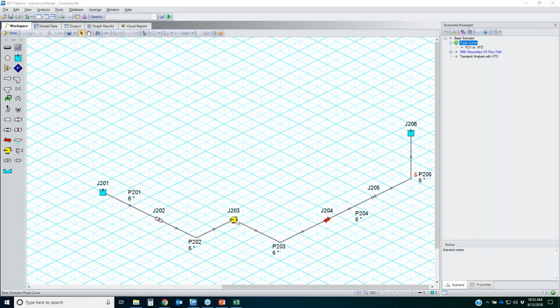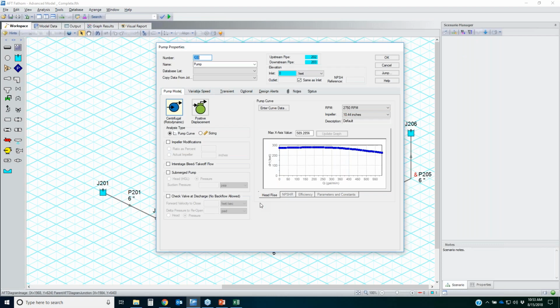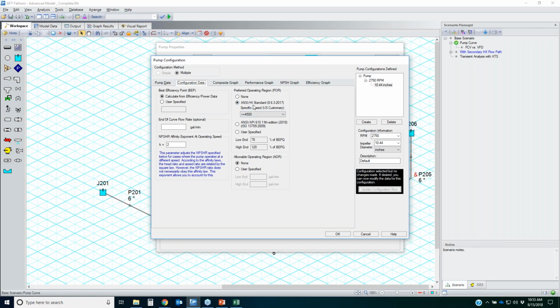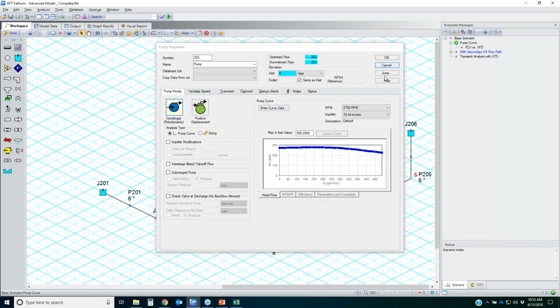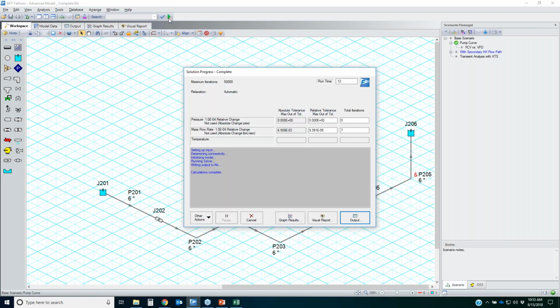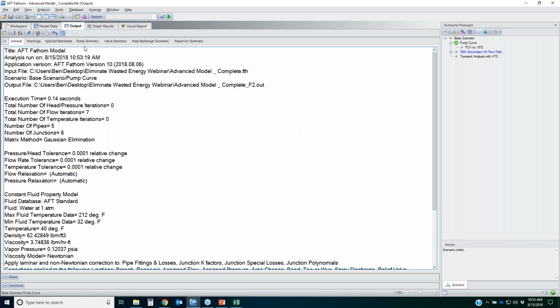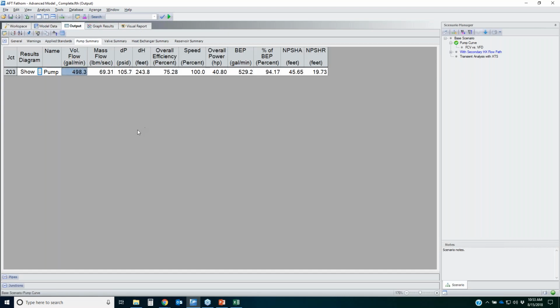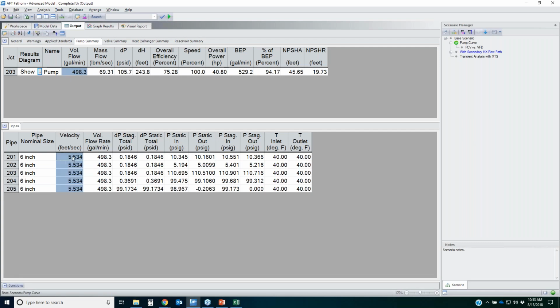Okay, and so I have a pump curve built into my pump property window, and in the enter curve data window here, I am going to turn on my preferred operating range. You'll see what that does. So when I run my pump, this is what the system was originally designed for. My design flow is 500 gallons per minute. Okay, so with this system being well designed for 500 gallons per minute, you can see that my piping velocities are below 6 feet per second. That's what I wanted. And if you look at the percent of the BEP, we're operating at 95% of the best efficiency point. So we're doing really good with our operation there.